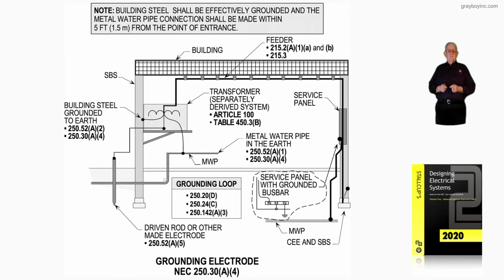Now this illustration deals with the grounding electrode. Where there's a separately derived system installed, then you've got to ground that secondary side of that separately derived system. But also you have to ground at the service equipment.